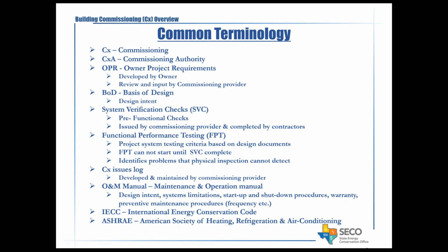FPT, which stands for Functional Performance Testing, is project system testing based on the design documents if it was new construction. If it's an existing building, that's a separate discussion I'll go over a little later. But mostly for new construction, you develop a system sequence of operation testing that meets the design intent.